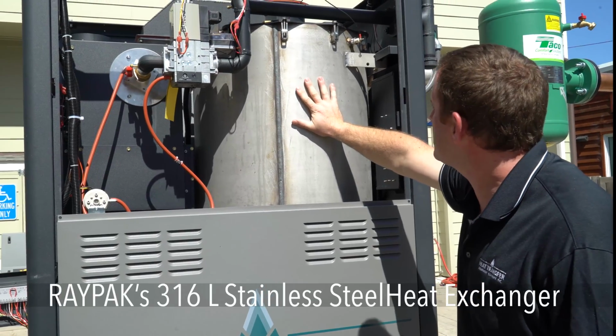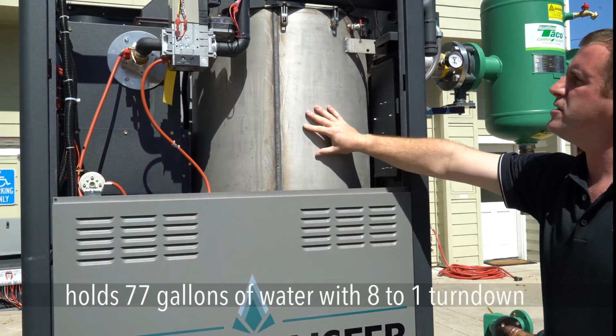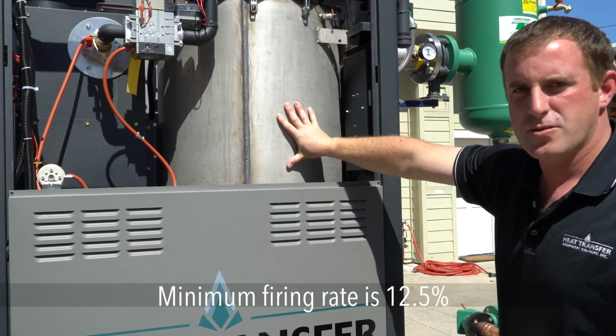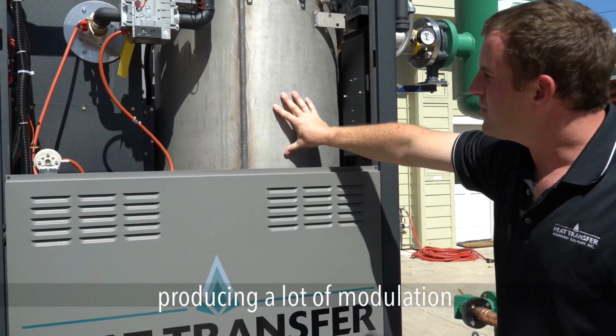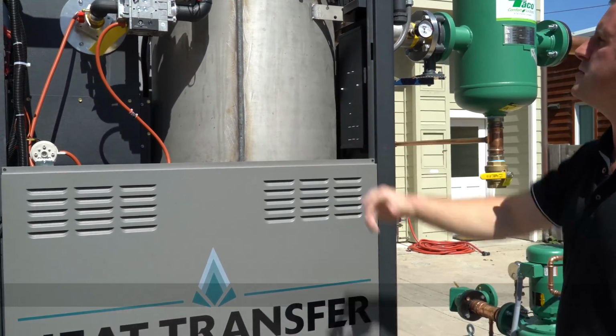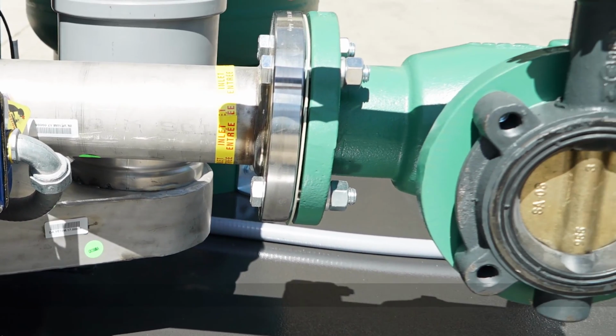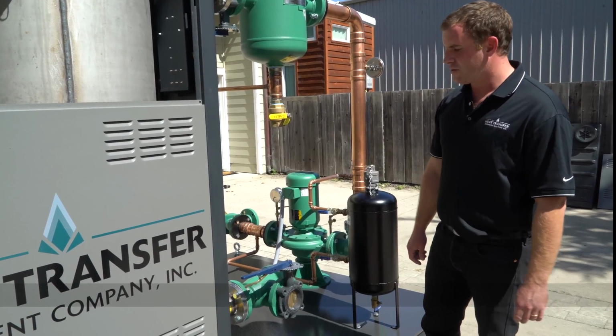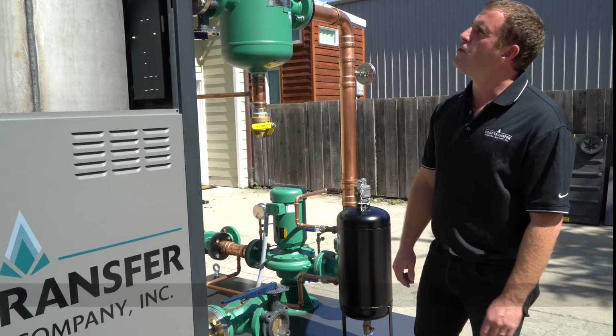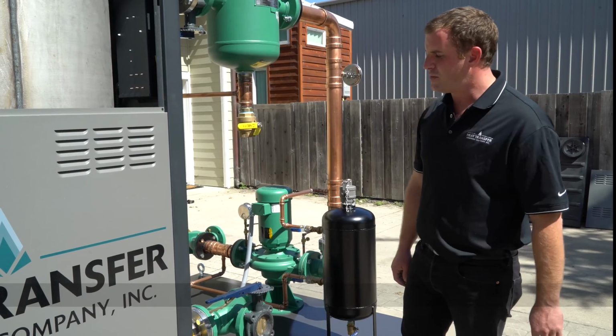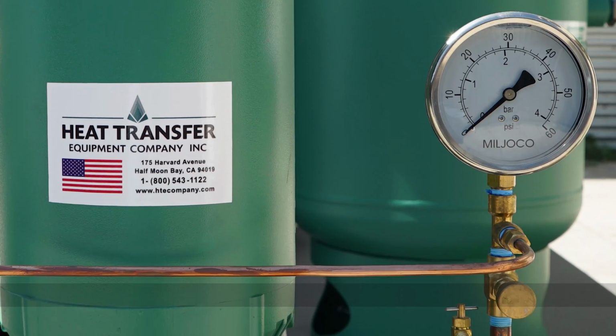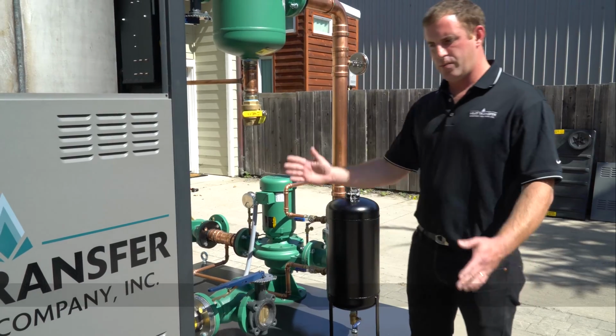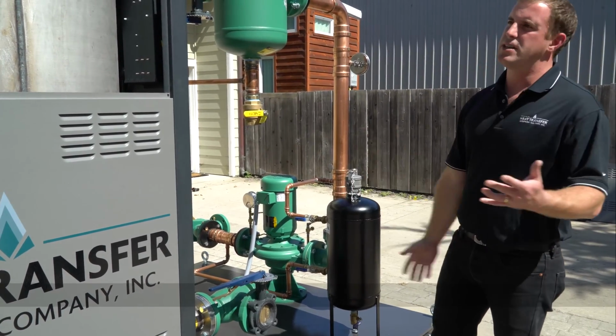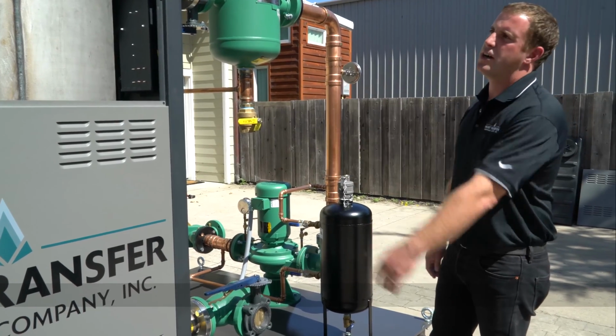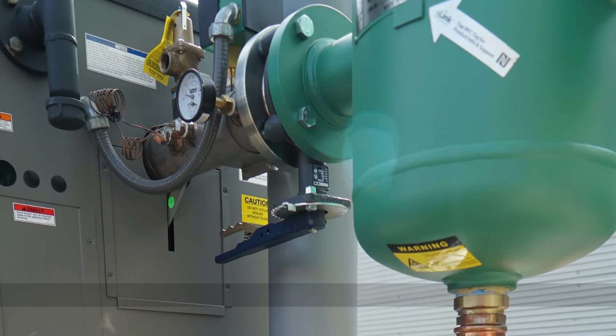This is a fire tube heat exchanger, holds 77 gallons of water, has 8-to-1 turndown, meaning that minimum firing rate is 12.5%. You get a lot of modulation for a boiler that is only 850,000 BTU. Electromagnetic flow meter will limit boiler high fire based upon what the flow through the unit is. Minimum flow requirement for full fire on this particular unit is 22 GPM. If this is turned down below 22 gallons per minute, the flow sensor will sense that and it will limit the high firing rate of the boiler so we don't exceed the maximum temperature differential across the heat exchanger, which is 80 degrees.